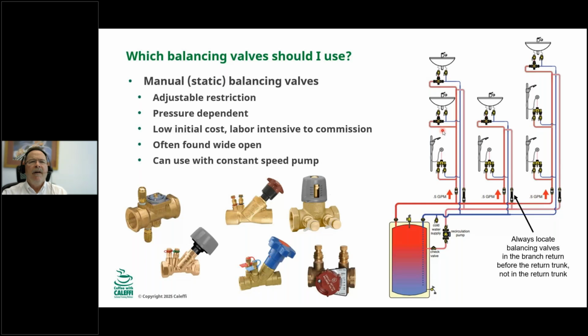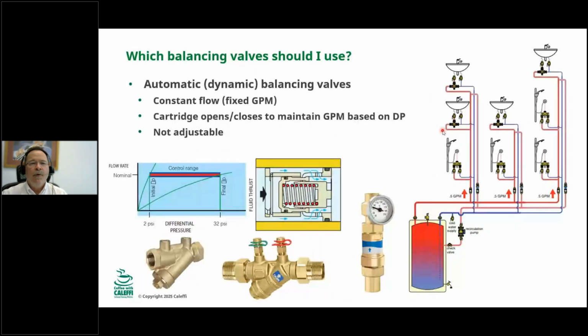The second valve, automatic, or what we call dynamic balancing valves. Think of these as a fixed GPM valve. They are a constant flow valve, and they're really, really cool how they work. Inside is a cartridge that has a spring in it. So as the fluid pushes against the face of this cartridge, it compresses the spring and pushes this cartridge in this direction to the right. And what that does is it will close and open the flow paths around the cartridge. So the fluid comes in here, goes around here, comes through this characterized opening, and then out.